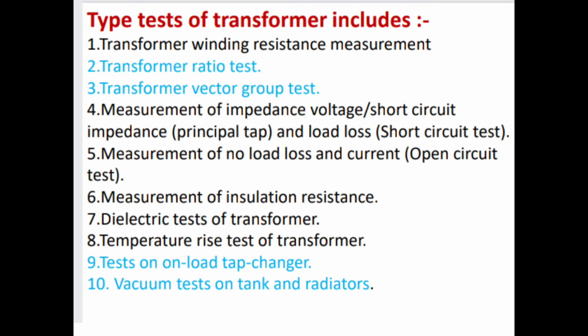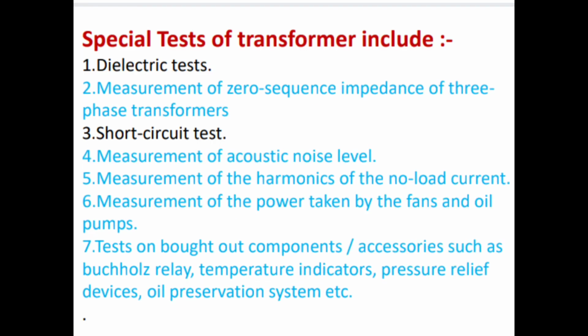Fourth is measurement of impedance voltage, measurement of no load loss and current, measurement of insulation resistance, dielectric test of transformer, temperature rise test of transformer, test on load tap changer, then the vacuum test on tank and radiators. Then the special test of transformer includes dielectric test and short circuit test. These are the main tests in the special test of transformer.